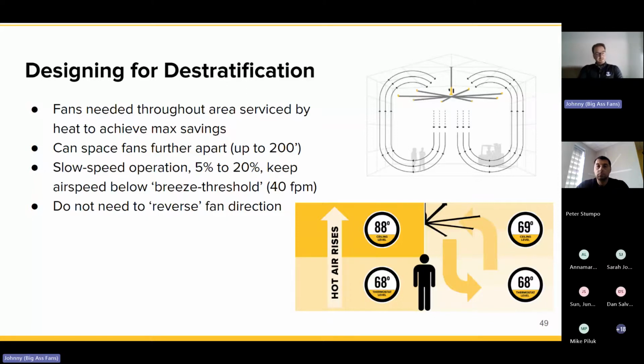Okay, so you can space fans a little bit further for destrat when we're designing these solutions. It's not as aggressive. We don't need full coverage of every square inch of that building for cooling or where the people are. We just need to get enough air turnovers per hour, which is what we measure to make sure that you're getting enough for destratification. So if your building was 1 million cubic feet of air volume, we want to make sure that we're getting at least 2 air turnovers per hour.